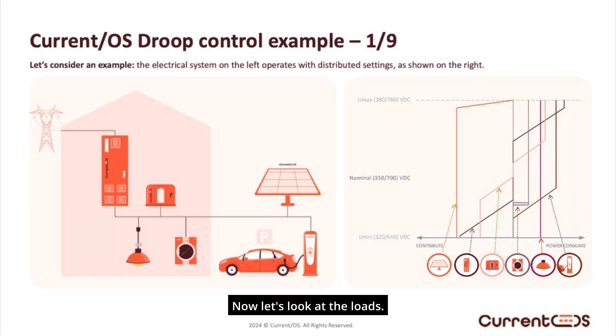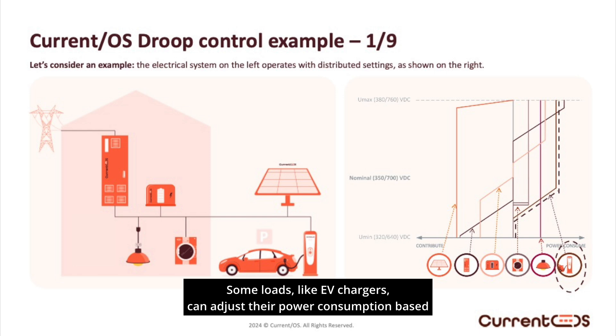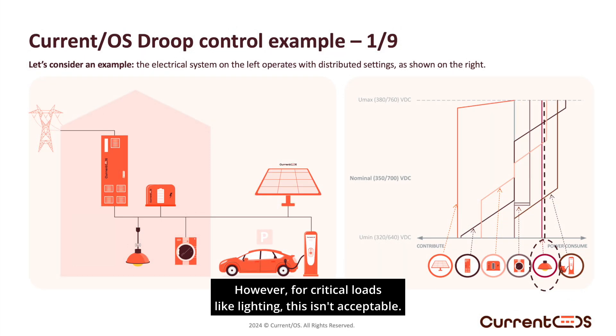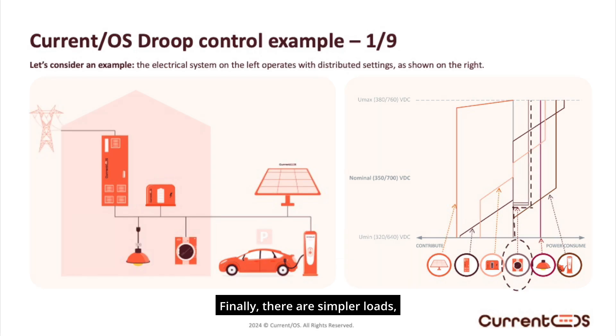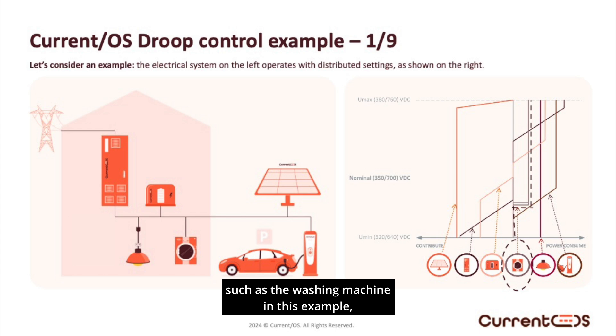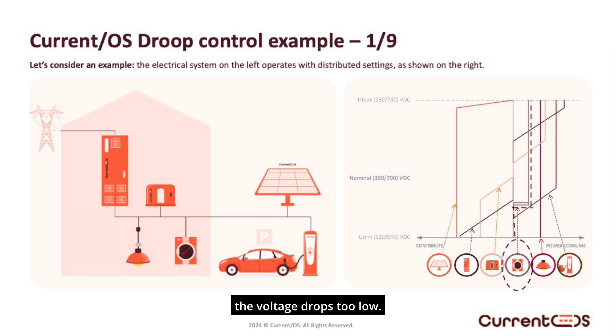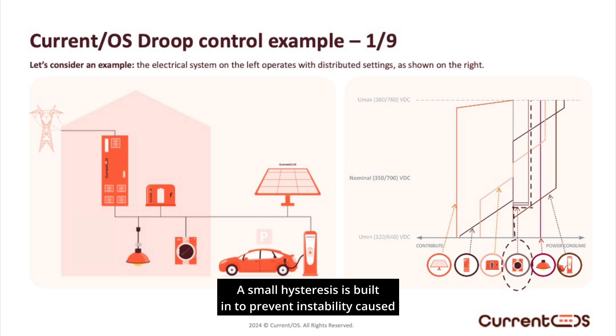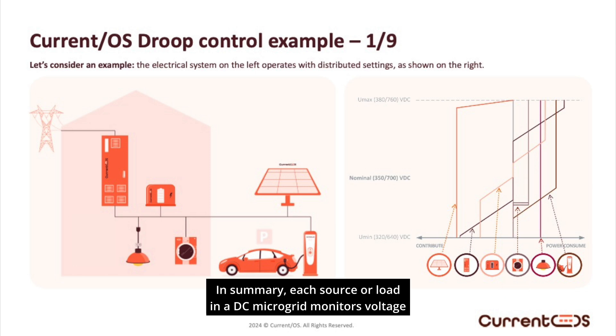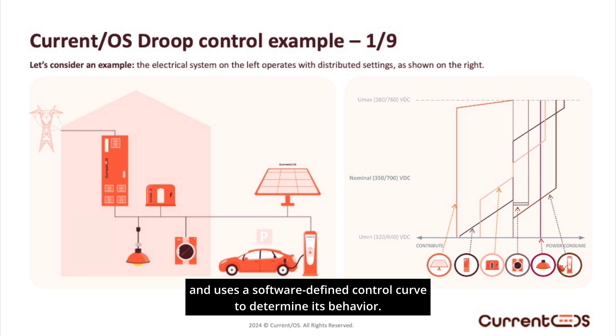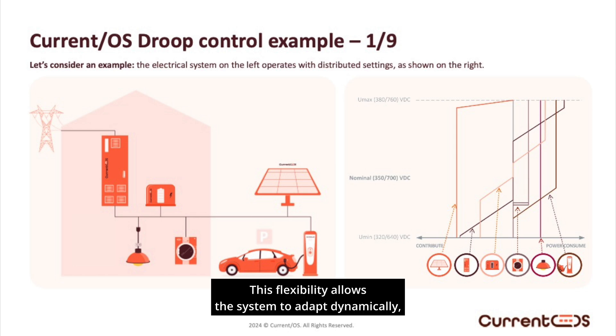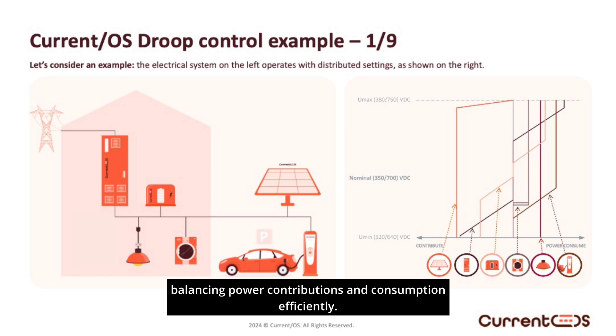Now let's look at the loads. Some loads, like EV chargers, can adjust their power consumption based on the available voltage. However, for critical loads like lighting, this isn't acceptable — they must operate at nominal power across the entire voltage band to ensure uninterrupted functionality. There are also simpler loads, such as a washing machine, which do not have gradual power adjustment. They operate at nominal power and stop entirely when the voltage drops too low. A small hysteresis is built in to prevent instability caused by frequent starts and stops. In summary, each source or load in a DC microgrid monitors voltage and uses a software-defined control curve to determine its behavior, allowing the system to adapt dynamically and balance power contributions and consumption efficiently.